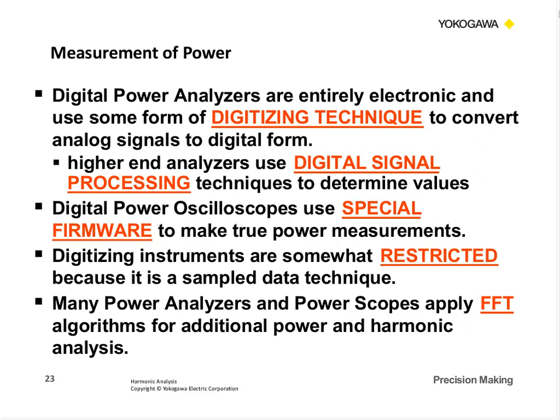How do we measure power? Well, on these distorted waveforms, all of our digital power analyzers are entirely electronic now, and we use some type of a digitizing technique. So we have digitizers on both the voltage and the current waveforms. And then we use digital signal processing to determine from those digitized values the actual measurement values. Now, a lot of digital oscilloscopes will have a power measurement function, and they will use a special firmware inside to make these true power measurements.